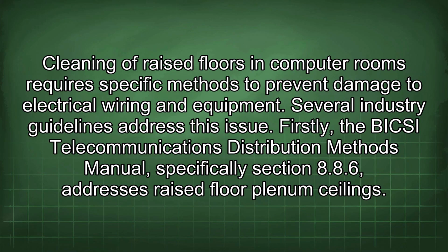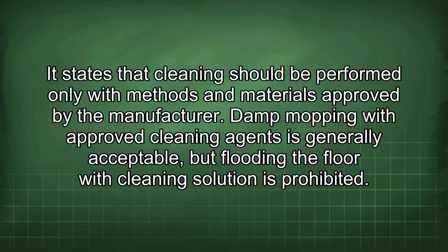Cleaning of raised floors in computer rooms requires specific methods to prevent damage to electrical wiring and equipment. Several industry guidelines address this issue. Firstly, the BICSI Telecommunications Distribution Methods Manual, specifically Section 8.8.6, addresses raised floor plenum sealing. It states that cleaning should be performed only with methods and materials approved by the manufacturer. Damp mopping with approved cleaning agents is generally acceptable, but flooding the floor with cleaning solution is prohibited.